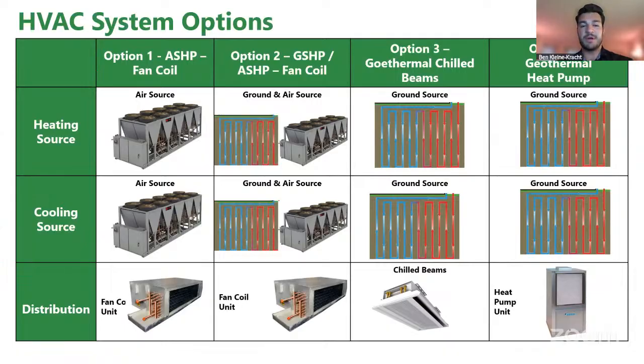Lastly, the geothermal heat pump. These are distributed water source heat pumps. So these come in sizes from a 0.5 ton to 15 tons. The catch with these is that they have the compressors and the refrigerant loop within each heat pump, and we like to put the heat pumps directly outside the classrooms. Typically, 2 classrooms are on 1 heat pump, and we would share the load between all the classrooms using the geothermal loop.